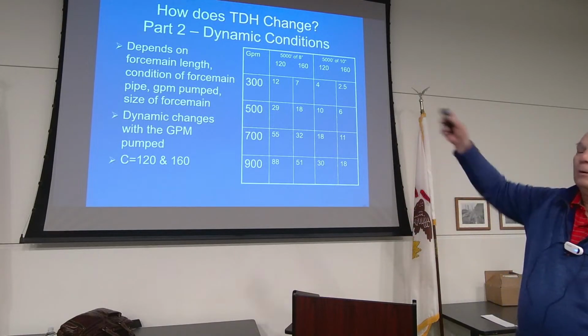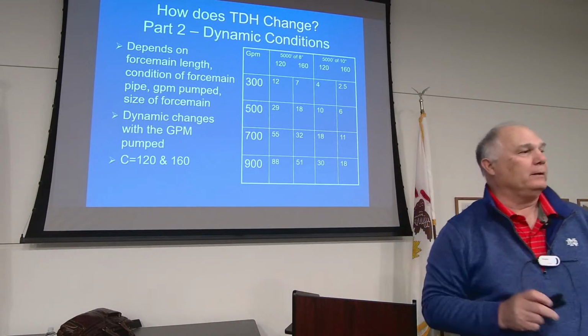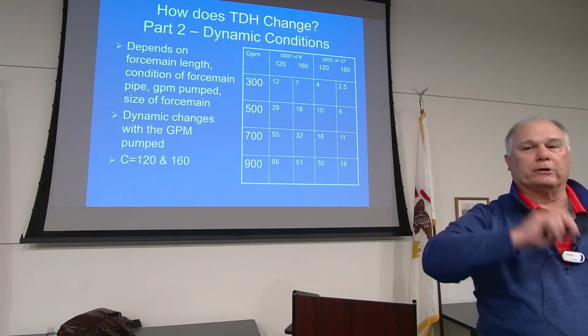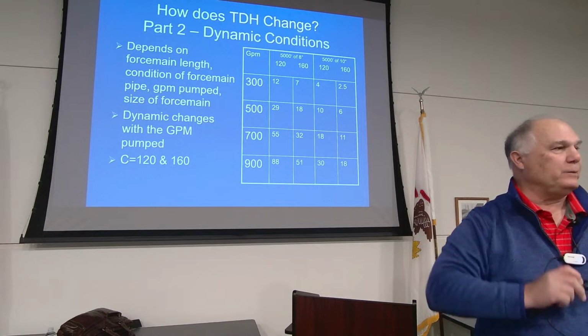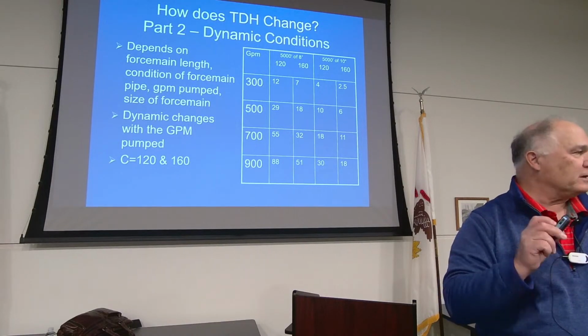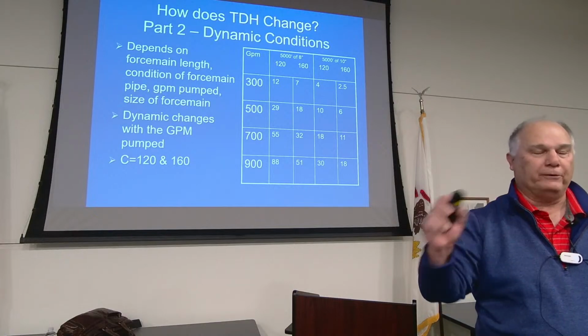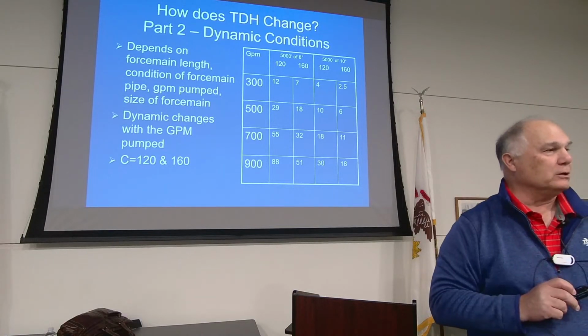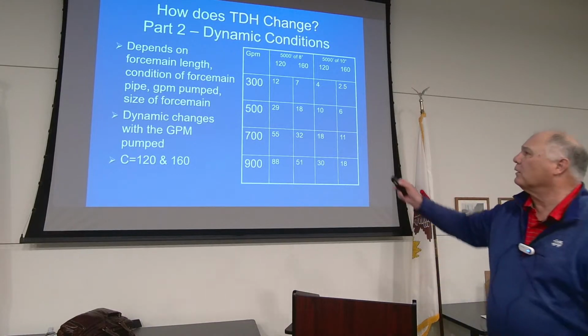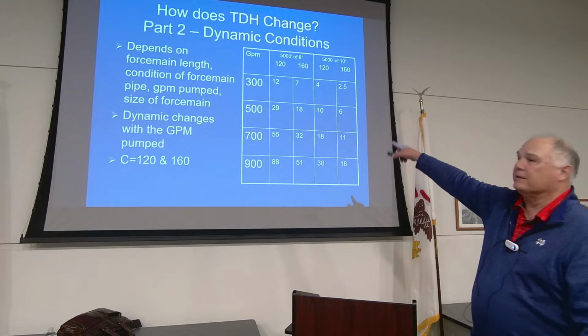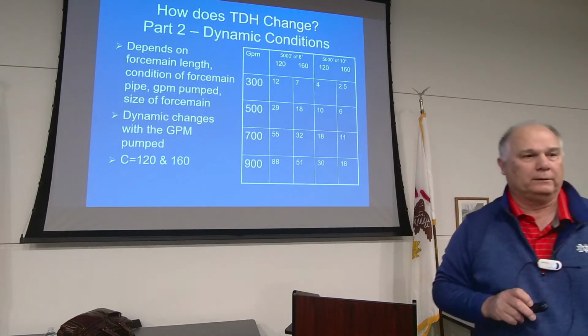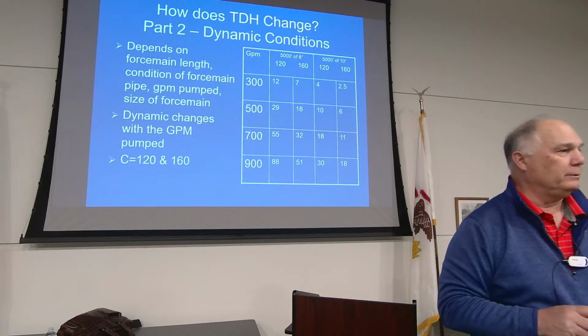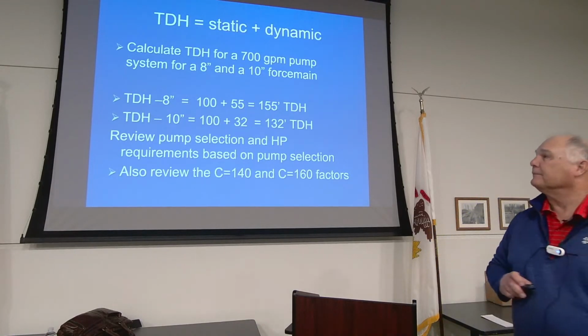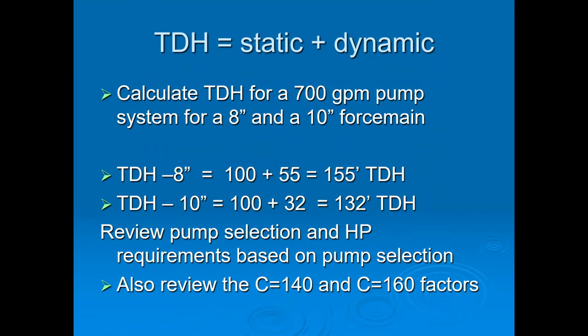But when you do a brand new pump station, brand new force main, what's the first thing you know you're going to do? You're going to exceed that GPM because you're going to have pipe that's slick as snot versus some 50-year-old pipe. When your C factor is higher, your head loss is lower. Therefore, we're going to be operating at a C factor of 160, not a C factor of 120. So we're going to have a lower head on that pump. But to get a TDH for that pump, now we know the volume we have to pump. Now we're going to add our static and our dynamic head to give us the TDH.